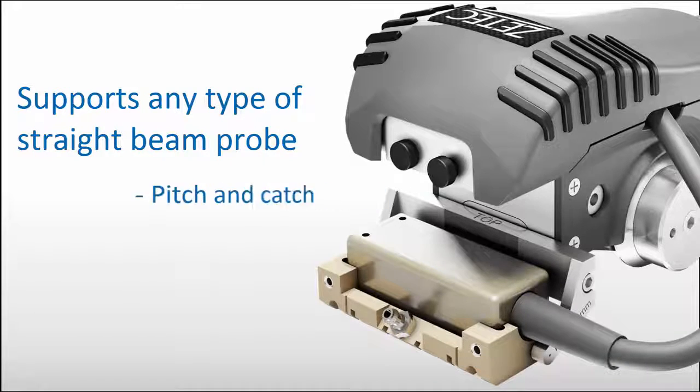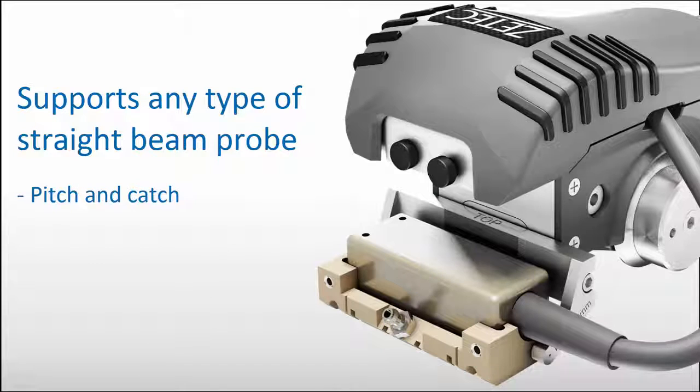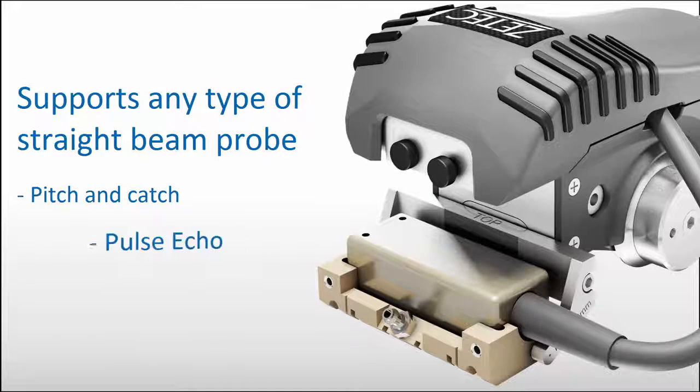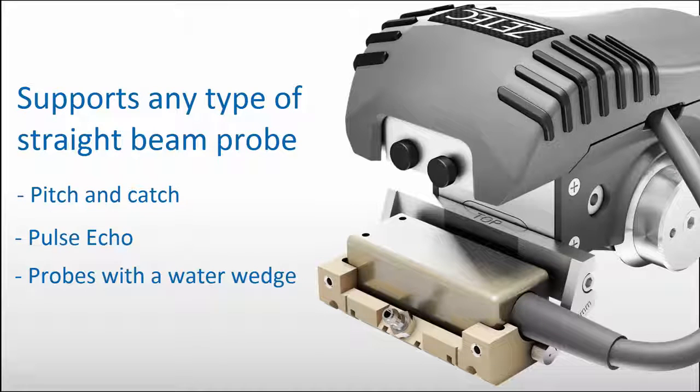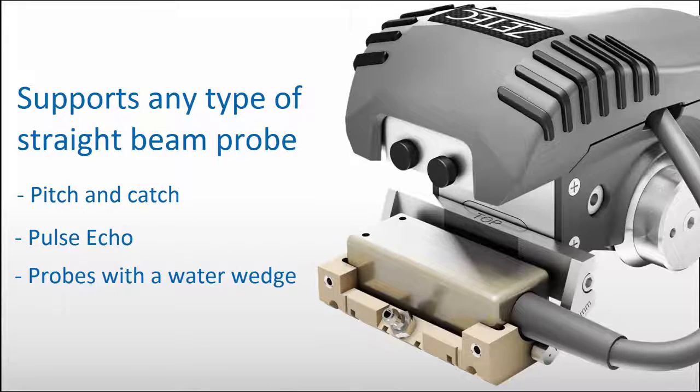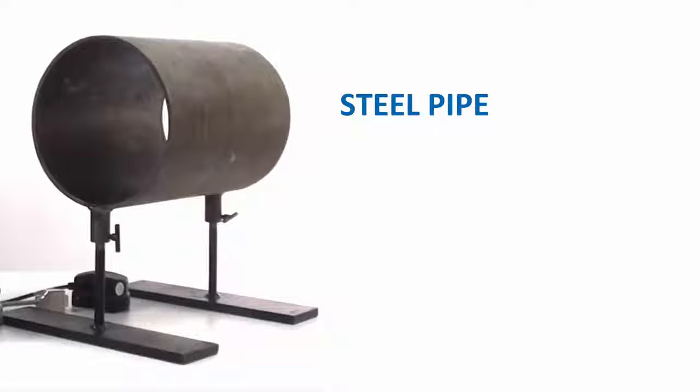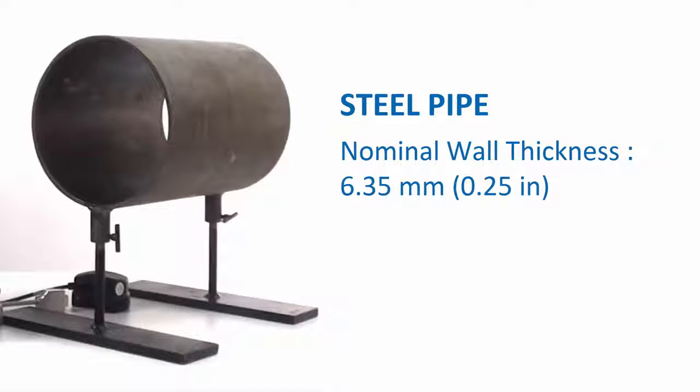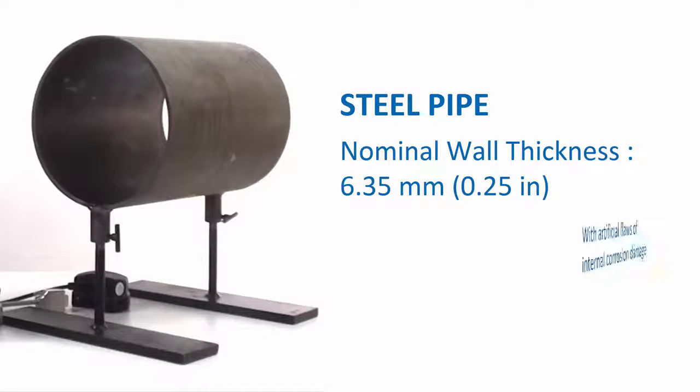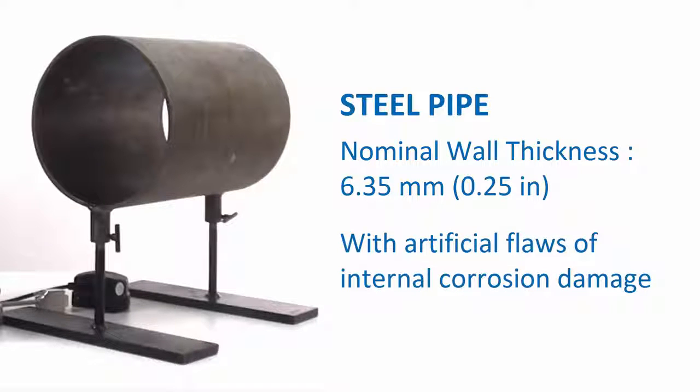Pitch and catch probes can be used for corrosion mapping on thin steel, as well as pulse echo probes or probes with a water wedge. The steel pipe considered here has a nominal wall thickness of 6.35 millimeters or a quarter of an inch. It contains artificial flaws machined to be representative of internal corrosion damage.